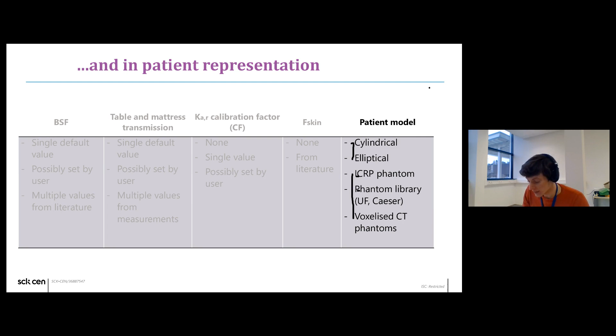And the current limitations of the skin dose mapping software products are, of course, all linked to those parameters and the patient representation as I just presented. To summarize the major limitations that still need to be addressed before having, let's say, perfect skin dose estimates, there are first the missing data fields in the RDSR. For instance, the air kerma calibration: only one value can be filled in the radiation dose structure report, although you would need much more to be accurate. And for the table and mattress transmission, no values are in the RDSR so far, as far as I know. And the field shape, the radiation field, is not really well defined in the RDSR. With the information in the RDSR, you are not able to represent it very accurately.